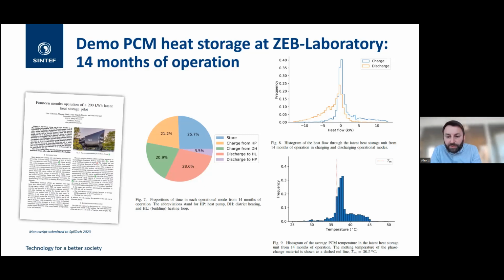Then you see also the temperature. The melting temperature is about the red line, the red dotted line on the graph on the bottom right. And here we see that probably when it was idle, it was charged actually. So it was above the melting temperature. And it seems to be staying quite a long time compared to the lower temperature. It's often charged and then discharged, and it doesn't stay much discharged, let's say, which makes it an even better point when you think of the heat loss that was calculated, that it's a quite low number, even so it's mostly at higher temperature than the melting temperature. So let's say that the temperature of the PCM storage is, there's a bigger difference between this temperature and the room temperature. So it should be an even bigger heat loss than if it was more average, let's say.